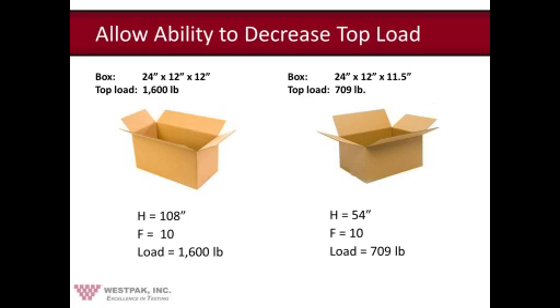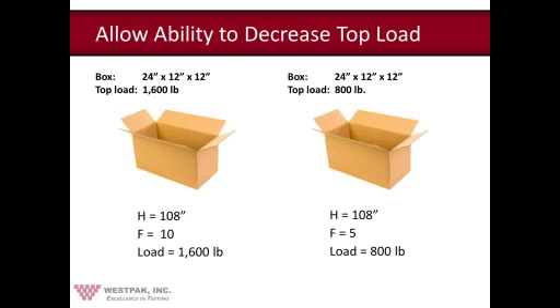Now you have the ability to write into your protocol what you want the H, or the height factor, to be. If you know your distribution environment, and if you know that packages will not be stacked over 54 inches or 60 inches or 72, whatever that may be, you can use that specific number for H in place of 108. Now in this example, we have 2 identical shippers that, again, are 2 cubic feet. At assurance level 1, which is the most conservative and most difficult level, the safety factor, which is F, is 10, and the target top load is therefore 1,600 pounds. However, you can write into your protocol the use of assurance level 3 or 2 for compression only, and that reduces the safety factor down to 5 or 7, based on if it's assurance level 3 or 2, and that would decrease the top load down to about 800 pounds, or half the amount. Now, prior to doing this, you really should understand your distribution environment and what inputs the shipper will be subjected to. Herb, do you want to go ahead and jump in here?